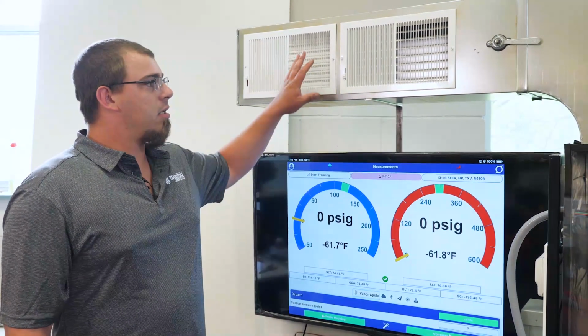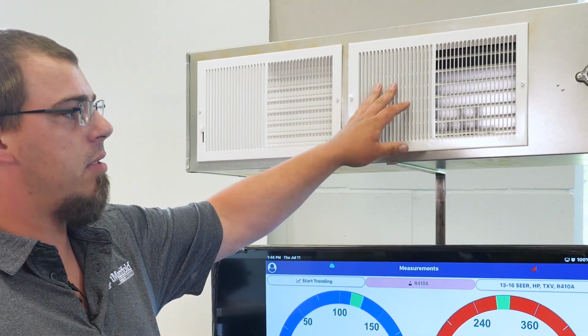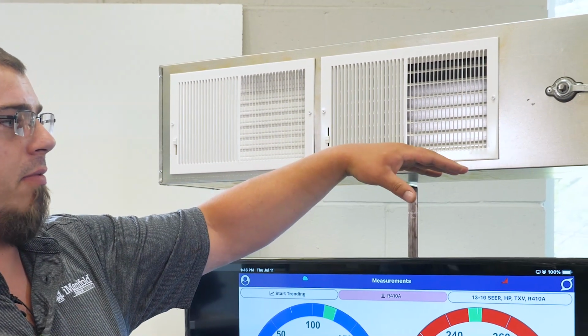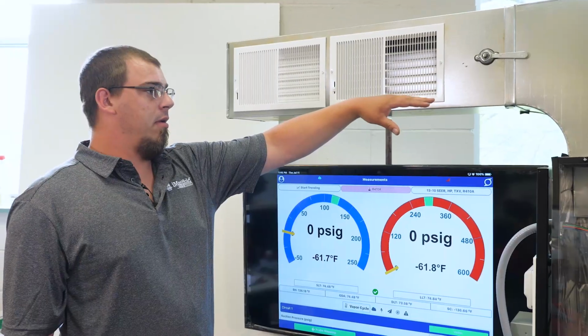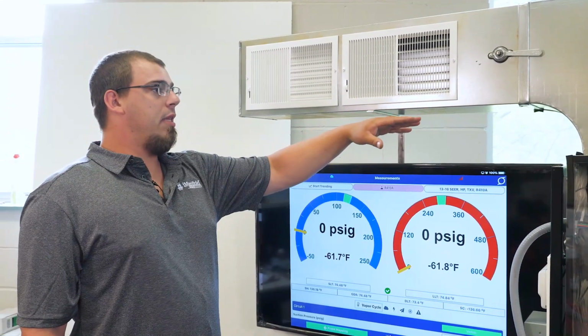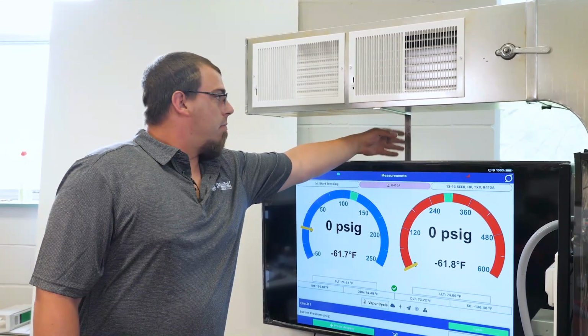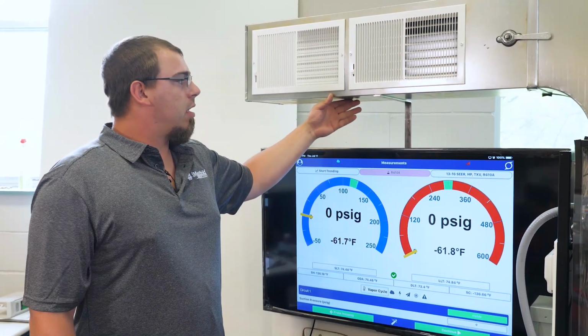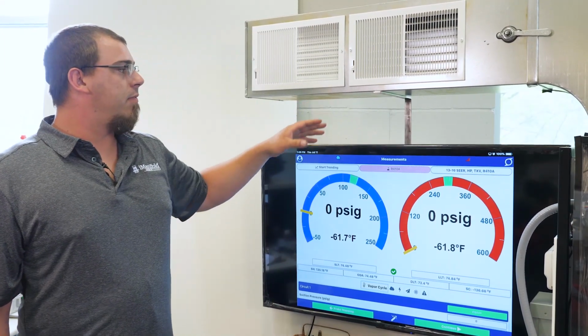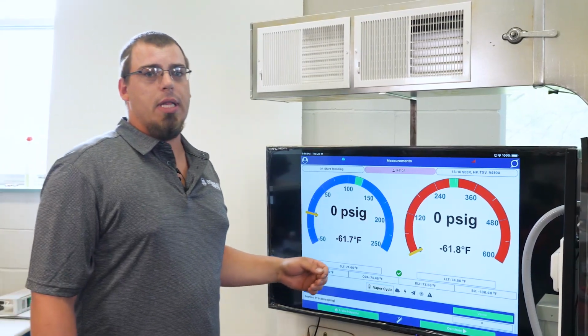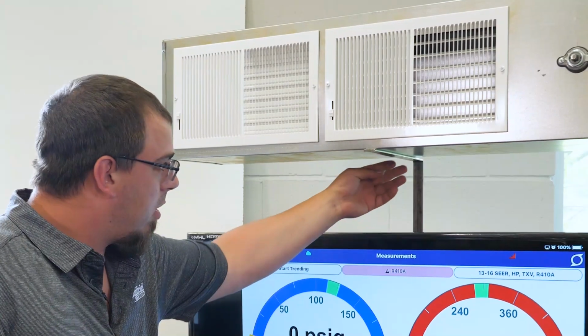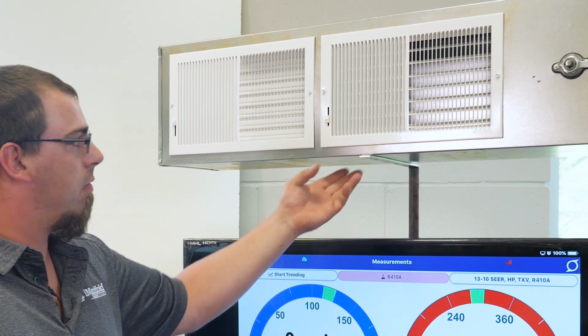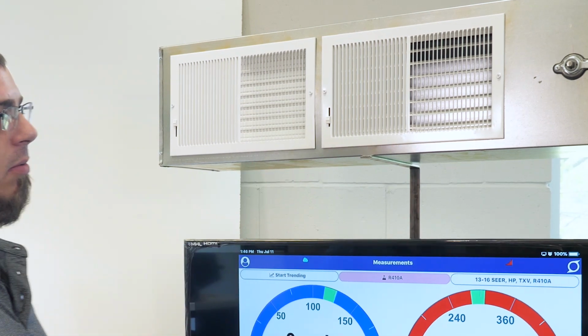We'll need to attach the ductwork. The registers are already installed. You'll just need to apply a couple of self-drilling screws to the top of the air handler. That'll secure it there. There is a mounting arm here to support the rest of the ductwork. That will have two self-drilling screws holding that up on the back, and then you can secure that here from underneath so the ductwork will be stable.